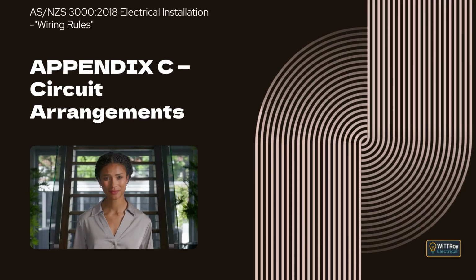Clause C 2.4.3.1, General. This clause explains that the alternative method uses typical energy demand values that depend on factors such as climate, hours of occupancy, energy management systems, and how evenly equipment is distributed. These values are used to estimate demand current for commercial and light industrial installations.